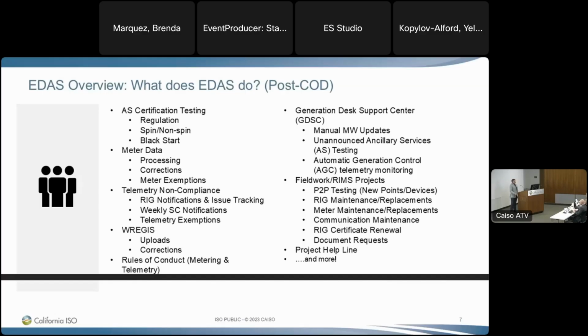More recently, we took over the AGC telemetry monitoring. We're looking at all the units that are off AGC where there might be a suspected telemetry issue. We call those SCs and tell them we see this unit is off AGC, we need you to submit an OMS card so we can zero out the AS and get this unit back into compliance. That really helps our operators focus on the issues that matter more to them rather than taking these telemetry calls.